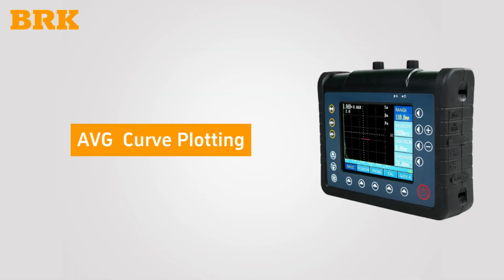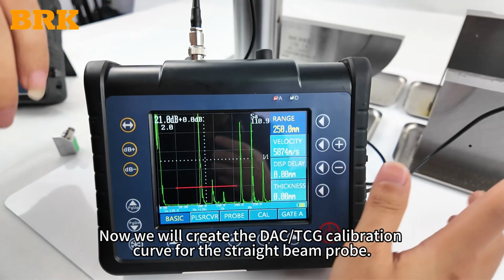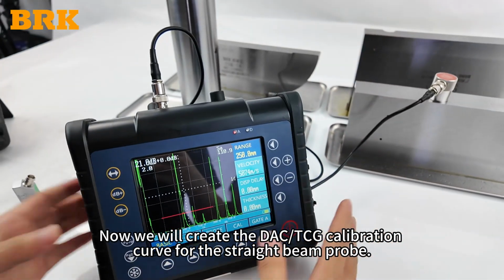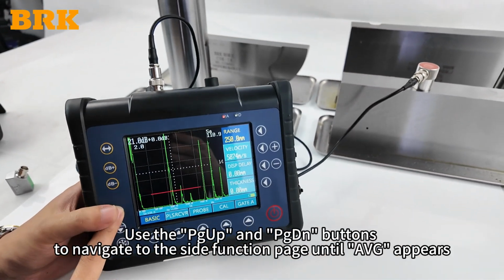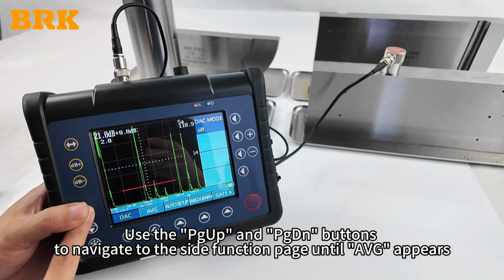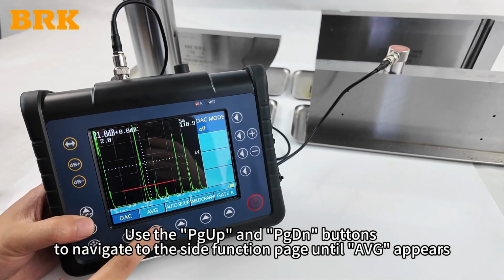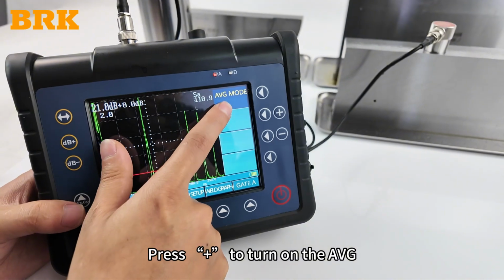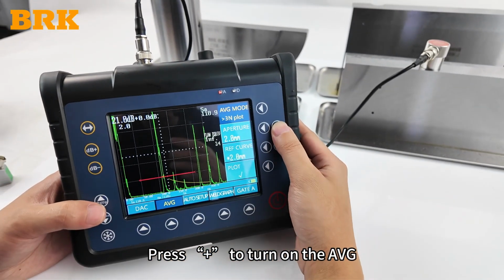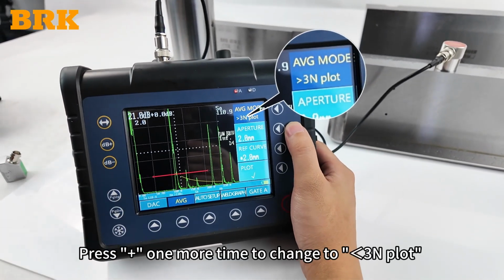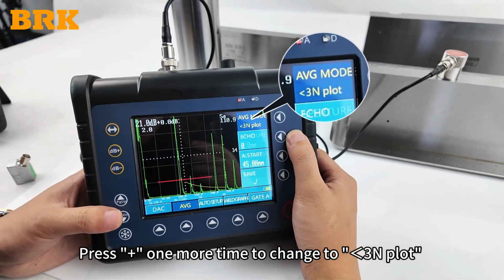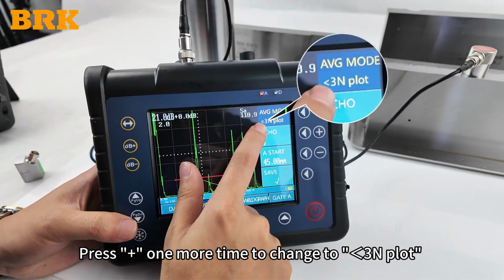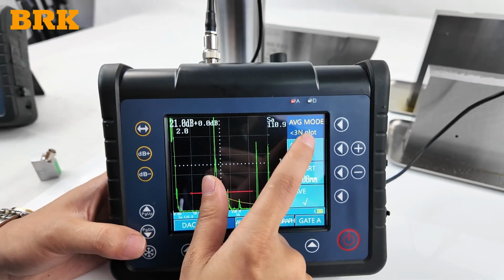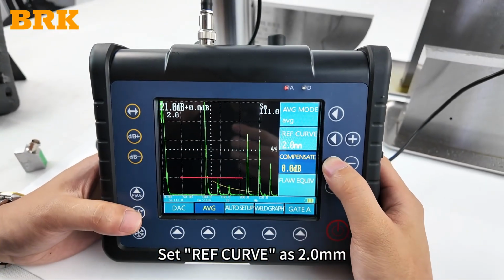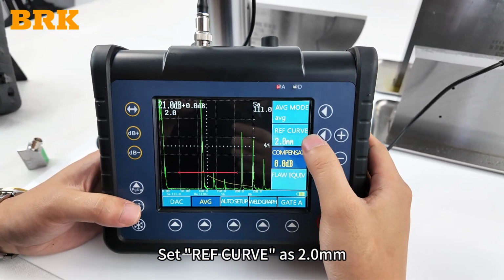AVG curve plotting. Now we will create the DAC or TCG calibration curve for the straight beam probe. Use the PgUp and PgDn buttons to navigate to the side function page until AVG appears. Press plus to turn on the AVG. Press plus one more time to change to less than 3N plot. Set ref curve as 2.0 millimeters.